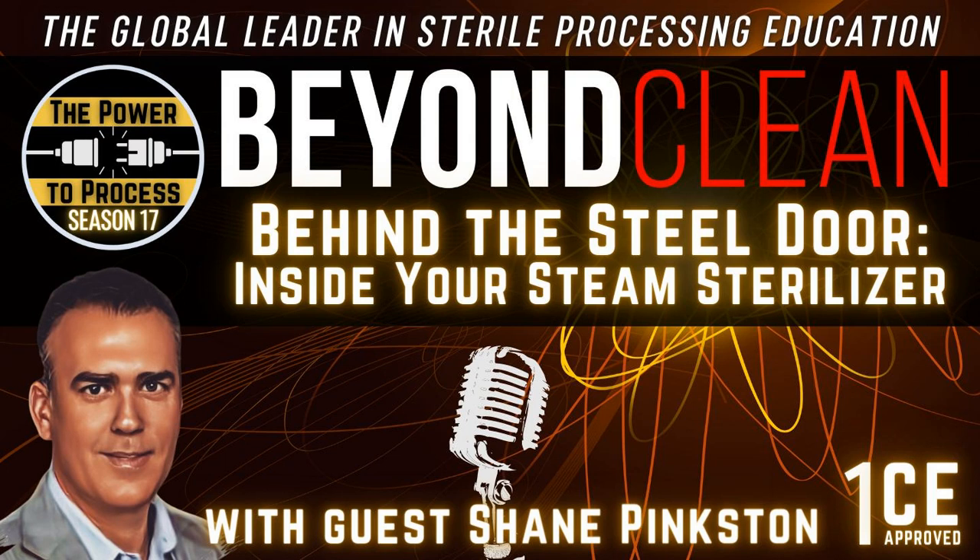So if it's that good, why do we get the funky smell? Why do we get the staining? Why do we get our favorite term — wet packs? Most of the time, I hate to tell you, it's not your sterilizer. It's the steam system ahead of it. So I think that's the big one.